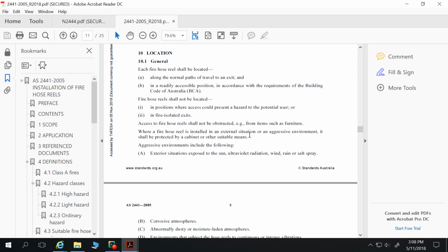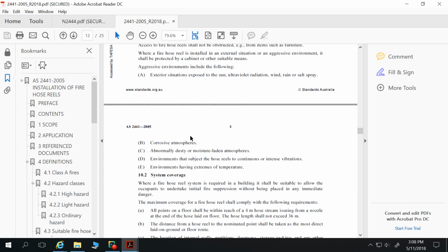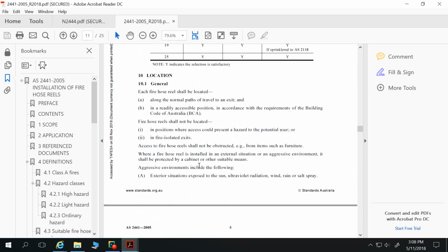So access to fire hose reels should not be obstructed by items such as furniture. Where a fire hose reel is installed in an external situation or aggressive environment, it shall be protected by a cabinet or other suitable means. I'm fairly sure we won't be installing any fire hose reels outside, so we don't need to worry about that. And these other aspects are probably not important to us. That's corrosive atmospheres or abnormally dusty or moisture-laden atmospheres, continuous or intense vibrations, environments having extremes of temperature. So the main thing we're considering is those fire hose reels being located along the normal paths of travel to an exit and in a readily accessible position in accordance with the requirements of the BCA.